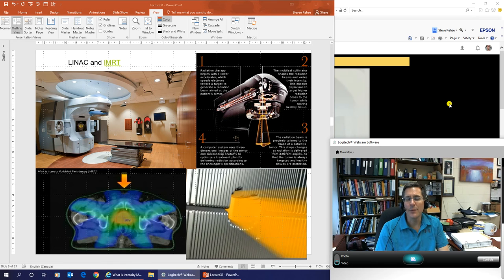Windsor Regional has three or four LINACs and they are in use all day, treating patients until 4:30 or 5 o'clock. Each patient session takes about 20 minutes, though the actual treatment itself is only 2 to 3 minutes. Technicians position the patient using laser beams on each side of the room that create a cross in space. That intersection point, exactly one meter beneath the x-ray source, is called the isocenter — the axis of rotation around which all treatment is planned.